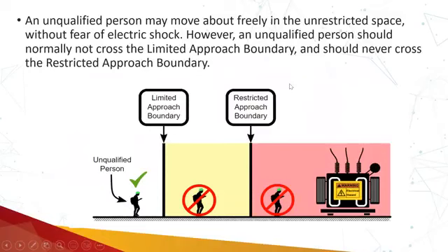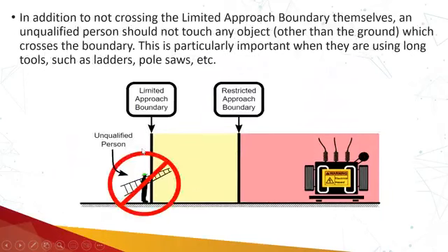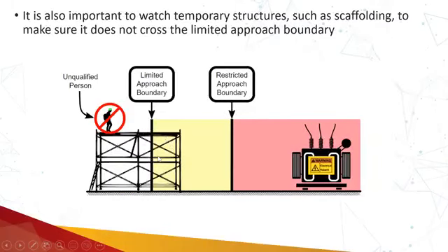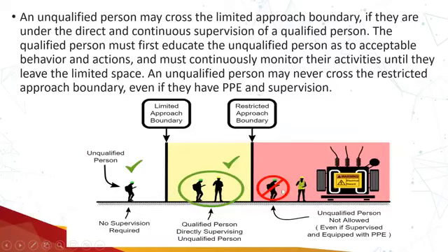Just to summarize, the limited approach boundary is basically the triggering point. Unqualified persons should be kept away from this limited approach boundary. They are not allowed to enter the limited approach boundary, and must never cross the restricted approach boundary. Long tools, handles, scaffolds or ladders are also not allowed to be brought into the limited approach boundary. Only qualified persons are allowed within the restricted approach boundary. The qualified person can escort unqualified persons who are within the limited approach boundary but not performing any tasks.